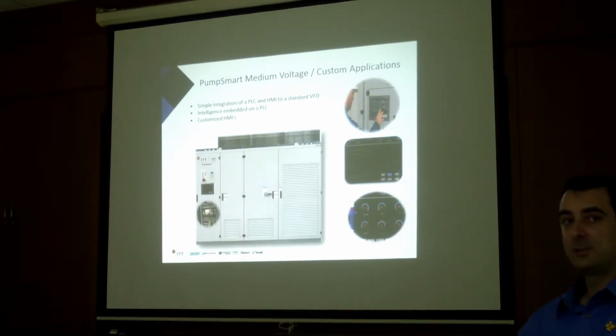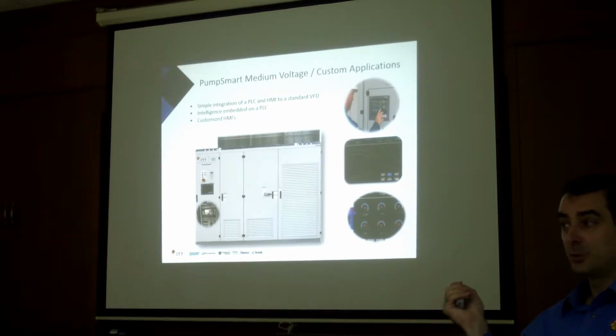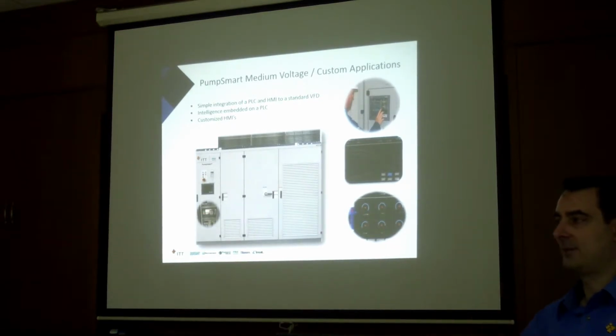Because we need good torque feedback from the variable speed drive. That's how our logic works. Many medium voltage drives, the good ones, will have that available. But in Rockwell, for example, they have a PowerFlex 6000, I think it's called, which we can use, but maybe we can't use the 3000 series because they don't have good torque. It's a cheaper, lower cost drive. So we do tend to need the more premium drive.